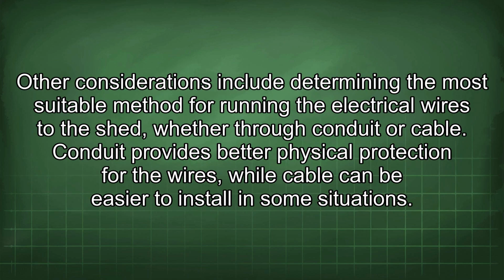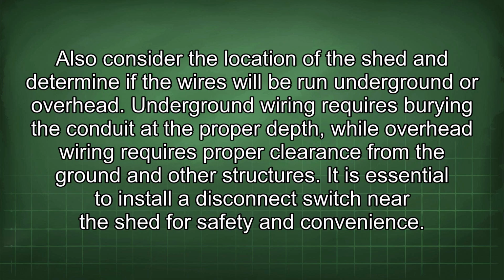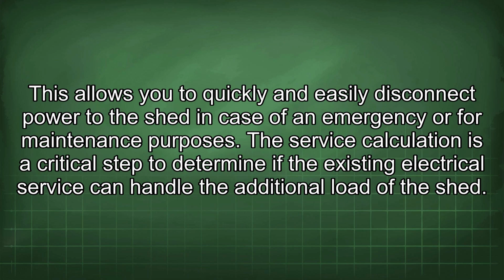Other considerations include determining the most suitable method for running the electrical wires to the shed, whether through conduit or cable. Conduit provides better physical protection for the wires, while cable can be easier to install in some situations. Also consider the location of the shed and determine if the wires will be run underground or overhead. Underground wiring requires burying the conduit at the proper depth, while overhead wiring requires proper clearance from the ground and other structures. It is essential to install a disconnect switch near the shed for safety and convenience. This allows you to quickly and easily disconnect power to the shed in case of an emergency or for maintenance purposes.